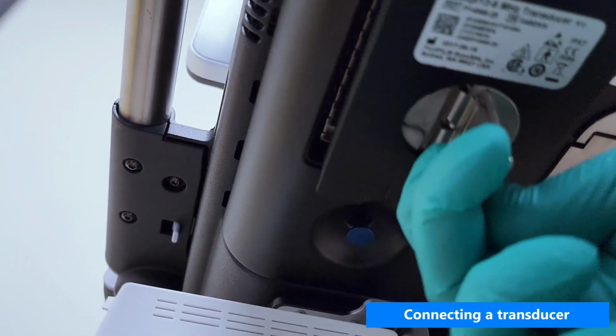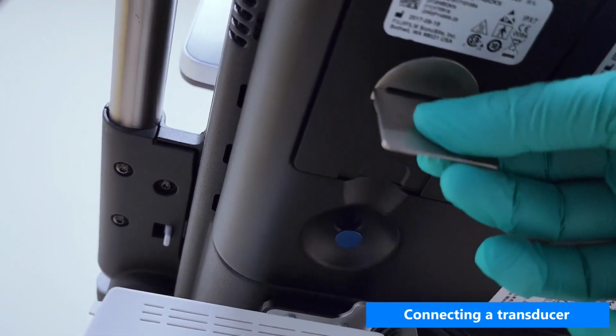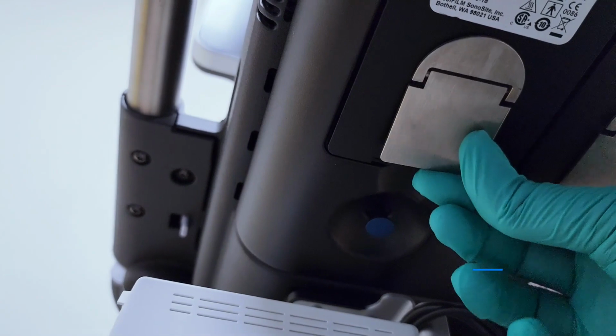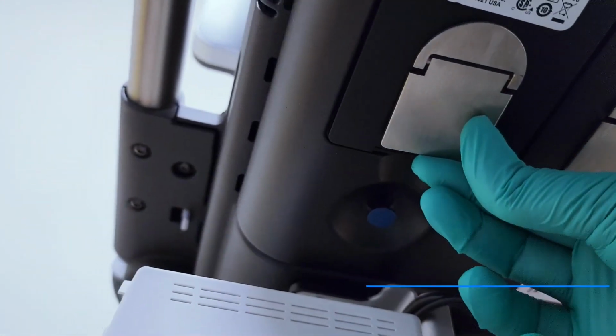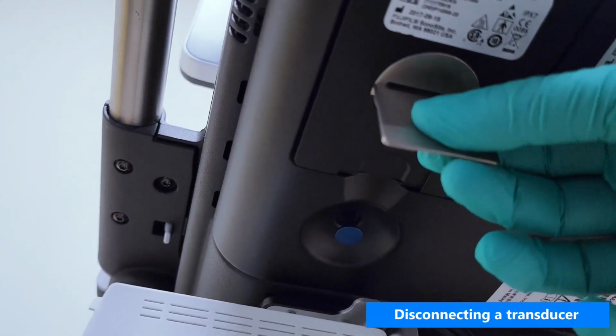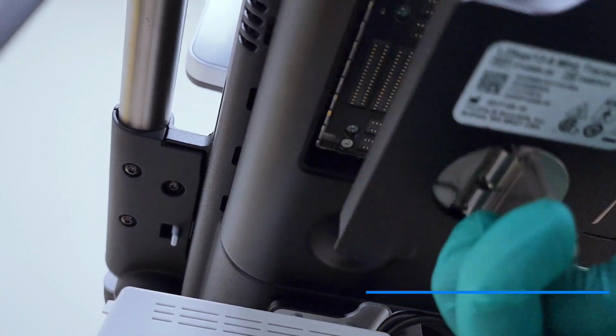To connect the transducer, look underneath the machine. Insert the transducer connector, turn the latch counterclockwise and press the latch down to lock it. To remove the transducer, pull the latch up and rotate it clockwise. Pull the transducer connector away from the system.